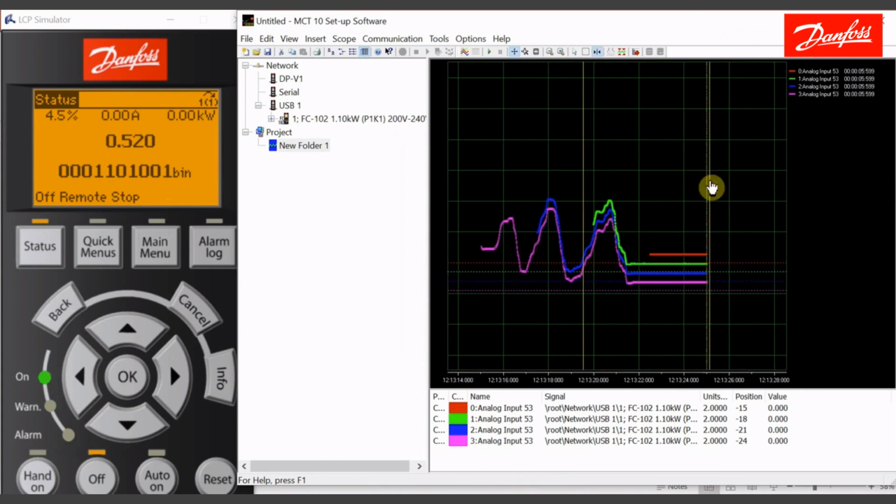That first channel, the red one, 5 milliseconds, that should be 2.5 seconds. The green one should be twice as long because it's polling at half the rate, and it is 5 seconds. 7.5 seconds. And the slowest one took 10 seconds to fill that buffer. So you can trigger on an event here, get good resolution, and then by changing those sampling rates, you can get a long trend over time.